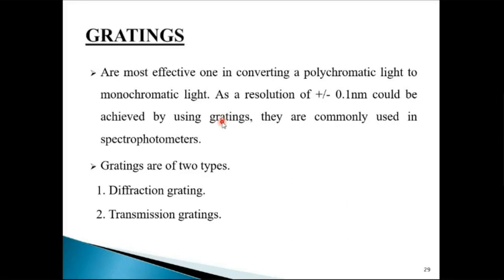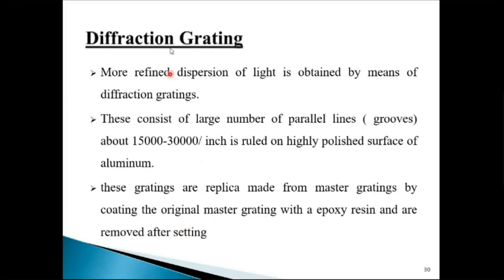In yesterday's lecture we saw that in spectrophotometers you get a wide beam of light or a broad spectra from which you need to select the wavelength for your analysis. The gratings are of two types: diffraction gratings and transmission gratings. Let us first start with diffraction gratings — more refined dispersion of light is obtained by means of diffraction gratings. When you say refined dispersion, it means the wavelengths are distinctly dispersed. These consist of a large number of parallel lines or grooves, about 15,000 to 30,000 per inch.